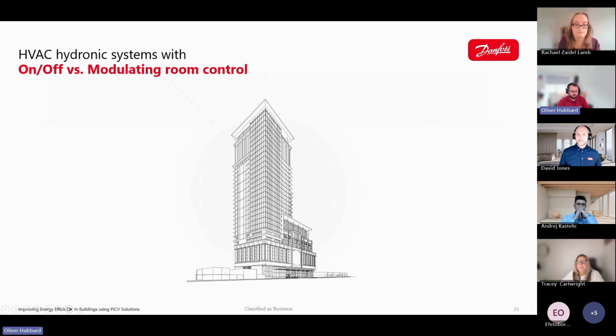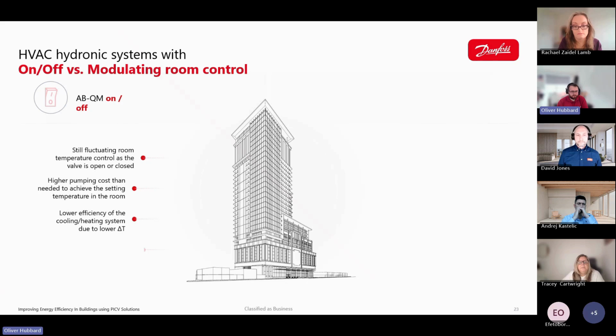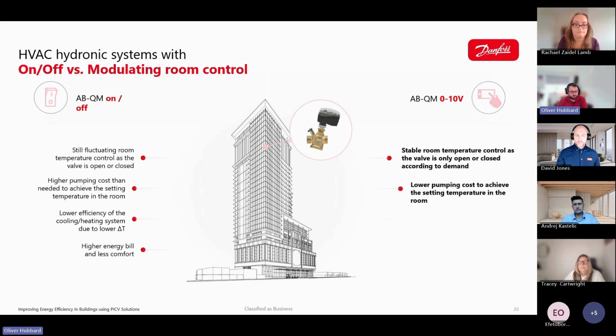So, hydronic systems with on-off versus modulating room control. The on-off room controls operate in a simple stop-start manner, delivering full heating or cooling until the set point is reached, and then shutting off completely. This often results in temperature fluctuations and inefficient energy use. In contrast, modulating room controls continuously adjust output in proportion to demand, maintain a stable room temperature, improving comfort and reducing energy consumption by only delivering exactly what's needed. The results are reduced bills and consumption, higher efficiency, lower pumping costs, and more stable room temperature, which overall increases comfort for whoever is occupying that room.